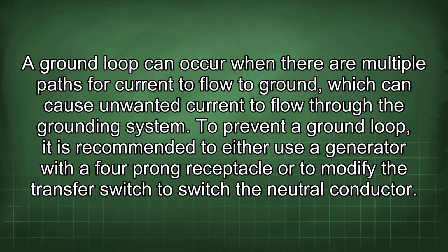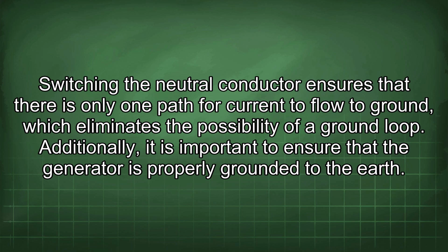To prevent a ground loop, it is recommended to either use the generator with a 4-prong receptacle or to modify the transfer switch to switch the neutral conductor. Switching the neutral conductor ensures that there is only one path for current to flow to ground, which eliminates the possibility of a ground loop.